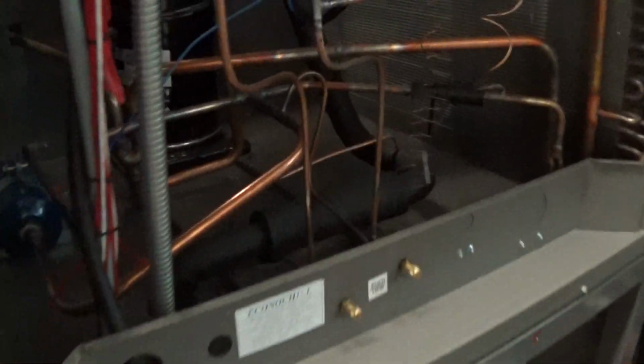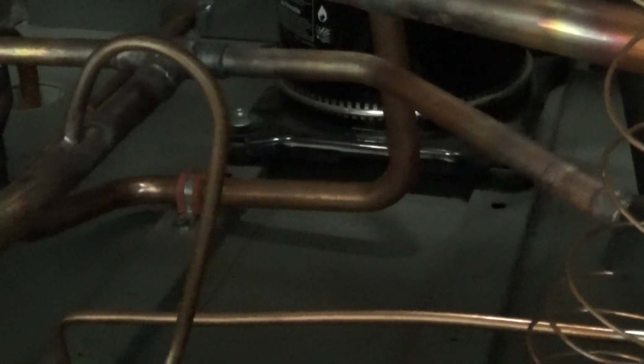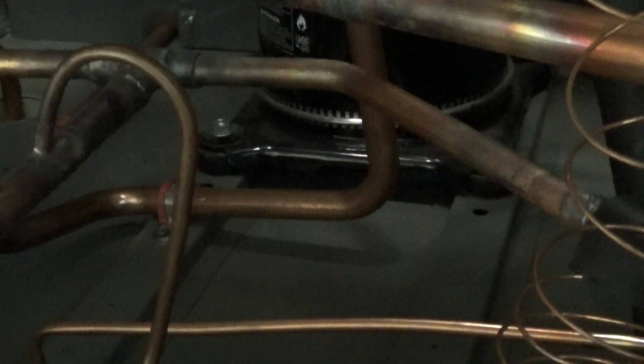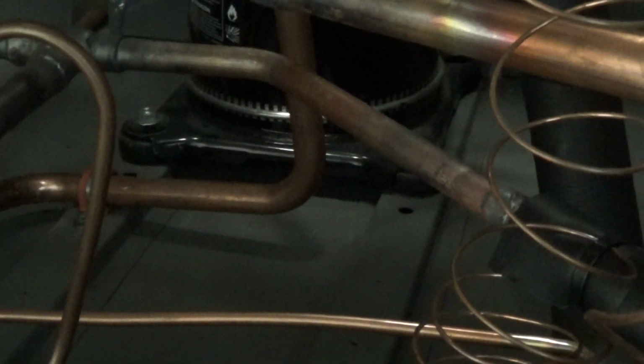The reason for that is if you see in the compressor here, it has a heater band around the base of the compressor. That's to keep the refrigerant warm and keep the refrigerant from gelling, if you will. You really want that on before turning the chiller on or operating the cooling. You really want that on for at least 12 hours. Even though the heater band's going to heat up quickly, the refrigerant inside there won't. And that's an important thing to keep in mind.